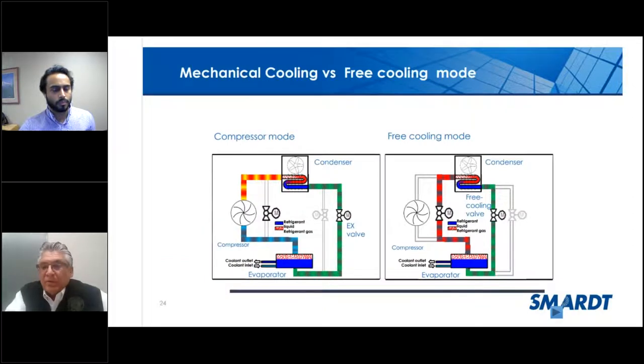So how many of you have had experience or had applications where you've been able to use free cooling or suggest free cooling in a water cooled application? You guys used much of that in the past? Yeah, I use that. So did you primarily do free cooling through a valved off plate frame heat exchanger to the cooling tower? Is that typically how you did it in the past? Yes, we did that, with a heat exchanger. I've also done free cooling with air cooled chillers too, where we had an additional module.